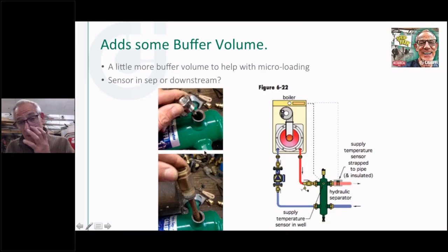All right, so think about this. Some of these boilers, in fact this little boiler that I've been showing you right here, hold a gallon of water, 1.2 gallons of water in that boiler. So that boiler can short cycle even on a low modulation rate if you've got a micro load on it.